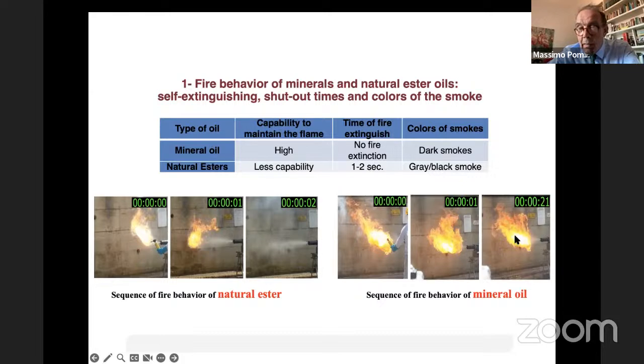So the spray remains on. So it means that when a fire starts in a mineral oil, it's not easy to switch off. Completely different in the case of natural ester. With natural ester, it's not easy to trigger the fire, even if we're using an external fire. For 1 second the fire remains on, but after 1 second, in 2 seconds, the flame is switched off.